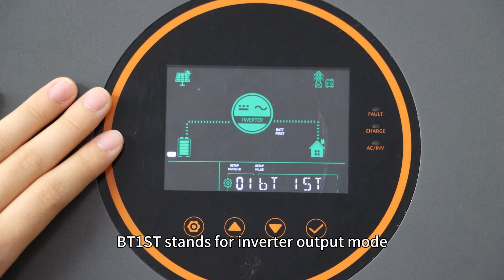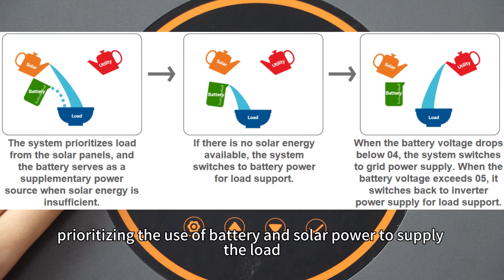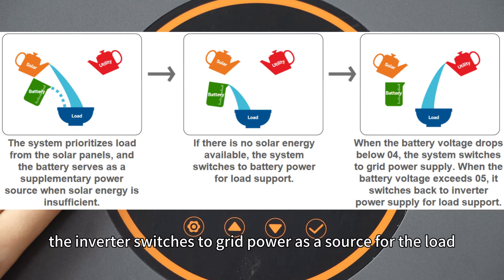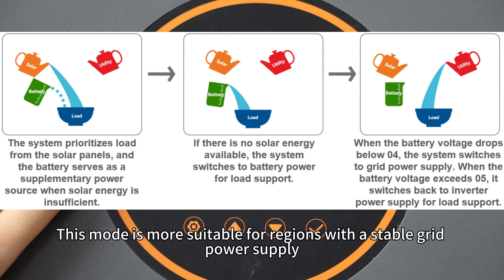BT-1ST stands for inverter output mode, prioritizing the use of battery and solar power to supply the load. When the battery voltage drops below the under-voltage determination voltage set, the inverter switches to grid power as the source for the load. This mode is more suitable for regions with a stable grid power supply.